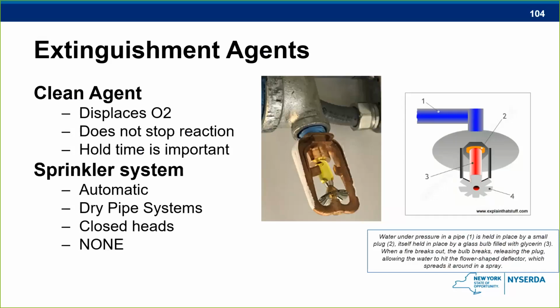If they don't prove it with the data, then you may require them to have another system in there that deals with water. So the sprinkler system itself could be automatic, or you could have a dry pipe system like we used in New York City. The reason that we went with dry pipe is because we were concerned about freezing weather. And if it was frozen and that water were to seep in there, well, now we just caused the problem that we didn't want to cause before.